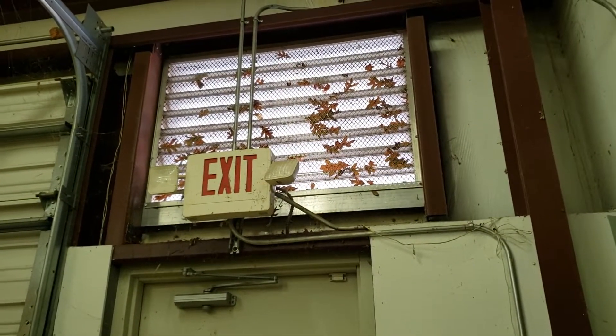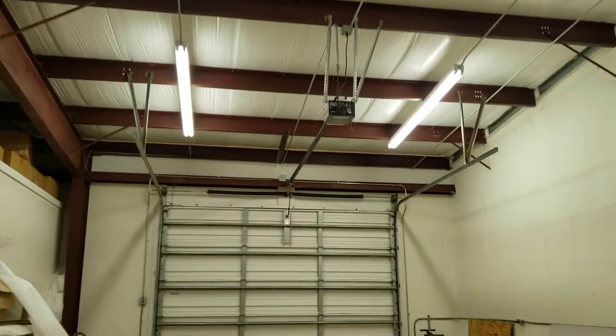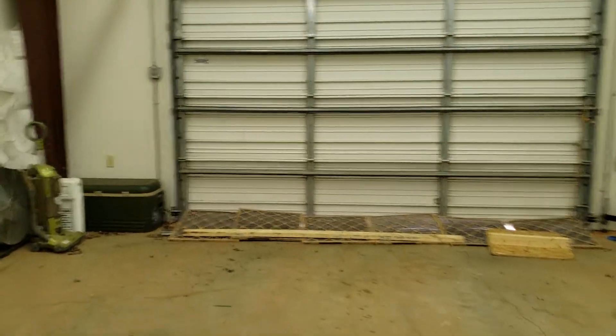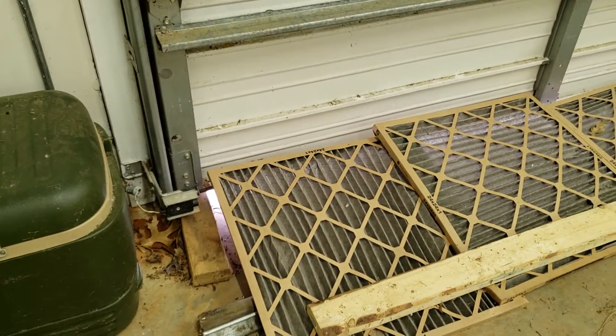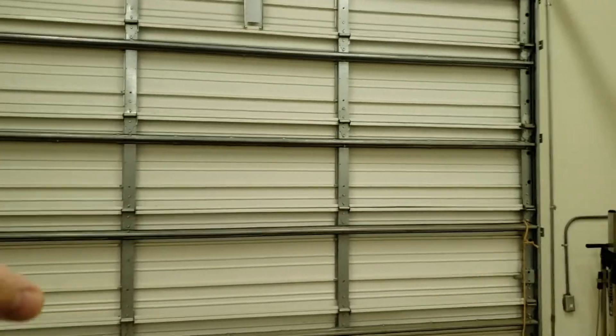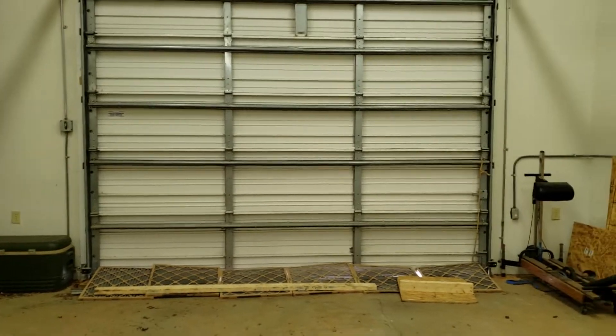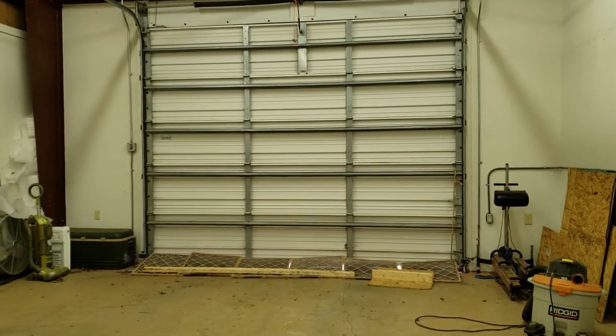These are things you want to make sure you do when bringing air into your facility — be conscious of the elements. This place happened to be extremely well sealed, so we were not getting the leakage we thought we were going to get. We didn't want to put too many cut-ins into the building because we'll have to repair it when we leave. To get some added air in and take off a little pressure, we had to jimmy-rig a system: we took off the flap at the bottom of the air door, put a two-by-four there to leave about a two-inch gap, and put a couple of filters. In a more permanent location, you could take out one of these panels and replace it with air filters or replace the entire door with air filters — but consider location, visibility, whether it looks abnormal, and whether it makes it a target. These are all things to consider as you're working with your airflow and design concepts.